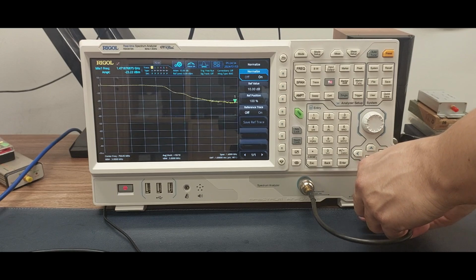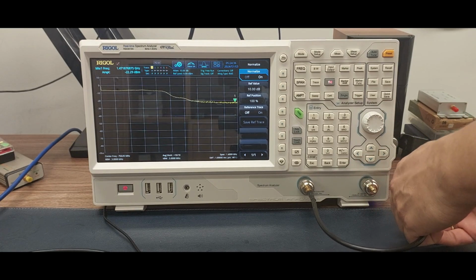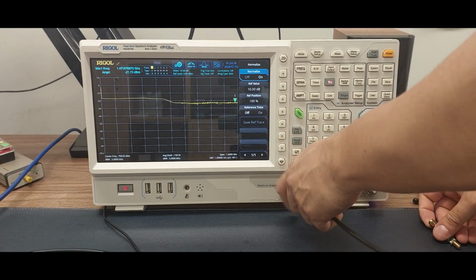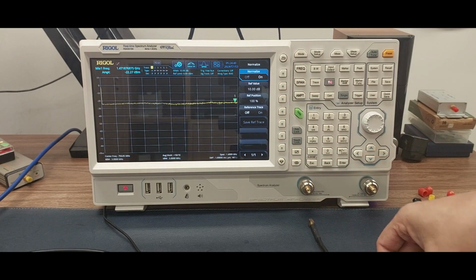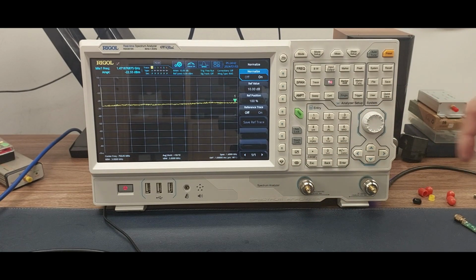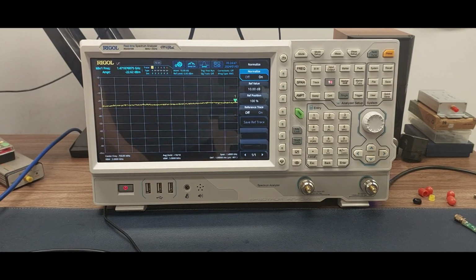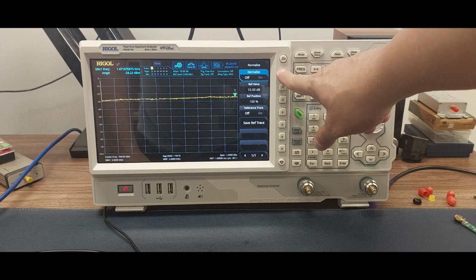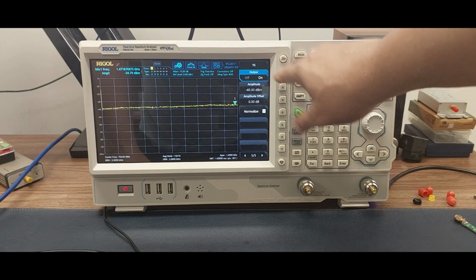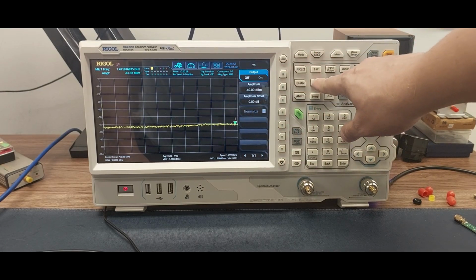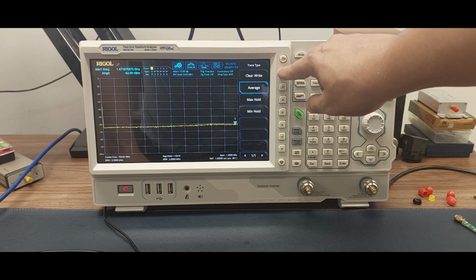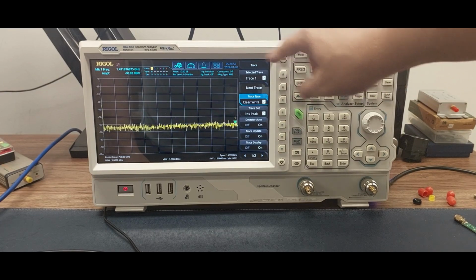So it works fine, the tracking gen, although this model specifically has a VNA available. So if I wanted to, I could go directly into the VNA mode and measure S parameters. It's not the point of this video though. So I'm going to turn off the normalization. I'm going to turn off the generator. I'll put the trace back to clear, right? So it's live again.